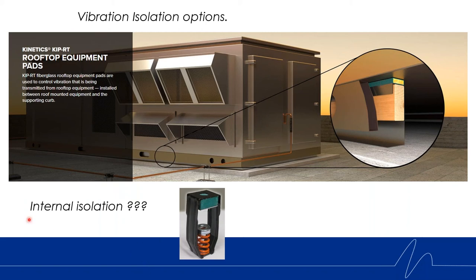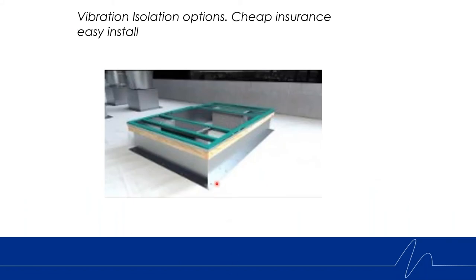We always get asked about internal isolation. Inside the air handling unit, the fans are sitting on springs already. Can we use those springs inside the unit? Well, when you're actually isolating that unit with pad, you can use the springs inside the unit under the fan. Springs and pad work in series all the time — it's a very good way to eliminate different ranges of vibration at different frequencies. So when you're isolating an air handling unit with a pad, you can still utilize the springs inside the unit itself.